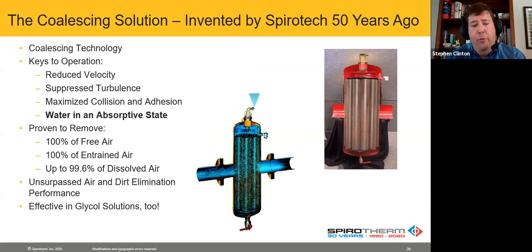That's the point of low solubility. So if we're at that point of 180 degrees and 60 PSI, 5.2 is the smallest amount of air that can be dissolved. We can remove 99.6% of that. So basically, we're unsurpassed in what we can do. We're also very effective in glycol solutions. Glycol is typically very difficult to deal with. It causes foam, and that foam basically makes it harder to remove air bubbles and also holds dirt.